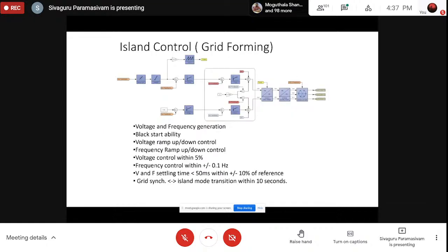Okay, so this is what we call island control or grid forming control. If you remember, I was telling you about the virtual synchronous generator. This is also known as grid forming. Which means there is no grid, but the power electronics and control system can form its own grid. This is not just on the scale of 1 kilowatt and 2 kilowatt. We have done projects with 10 megawatts and 30 megawatts with grid forming. There is a huge township, and the huge township is just working with grid forming inverters alone. I mean 30 megawatts of inverters, all connected in parallel.